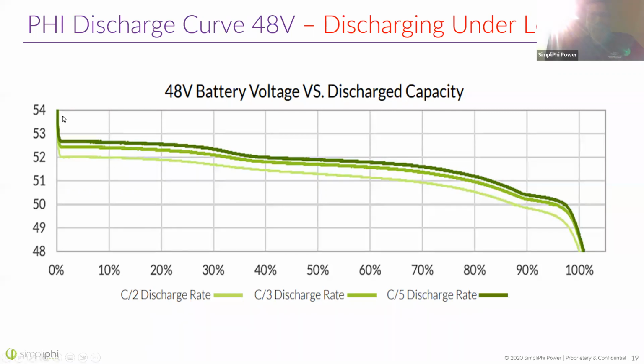Looking at these graphs, the discharging under load voltage starts out right around 53 volts, indicating 100% state of charge, 0% discharged. But because of the loads, the battery voltage drops down. Notice that for C/2 discharge rate, the battery voltage drops to 52 volts fairly quickly. In other words, when pulling the maximum amount of current out of a battery, the voltage will drop by about a volt.